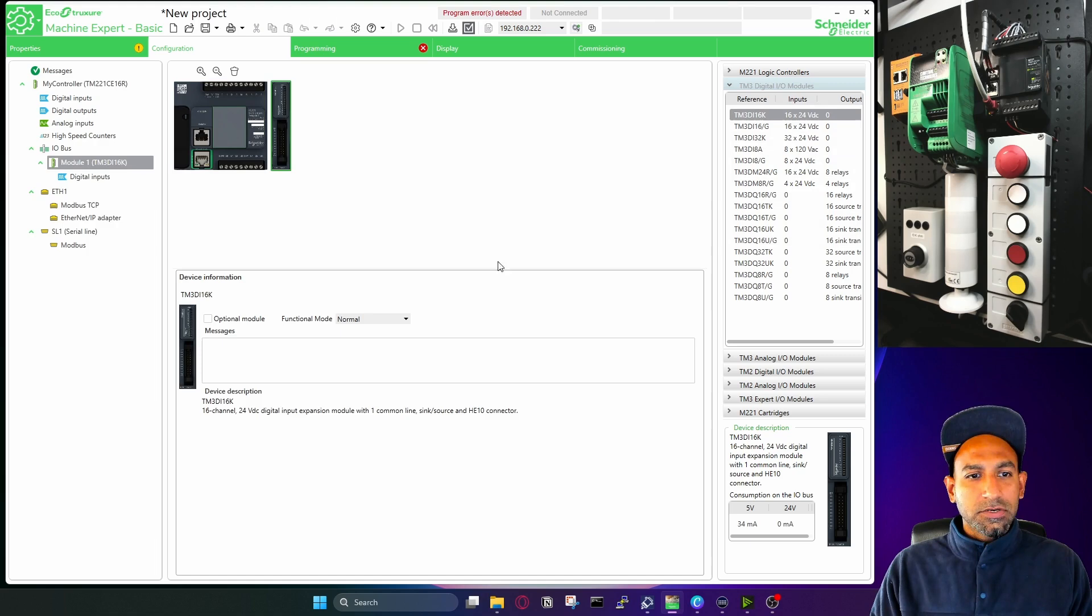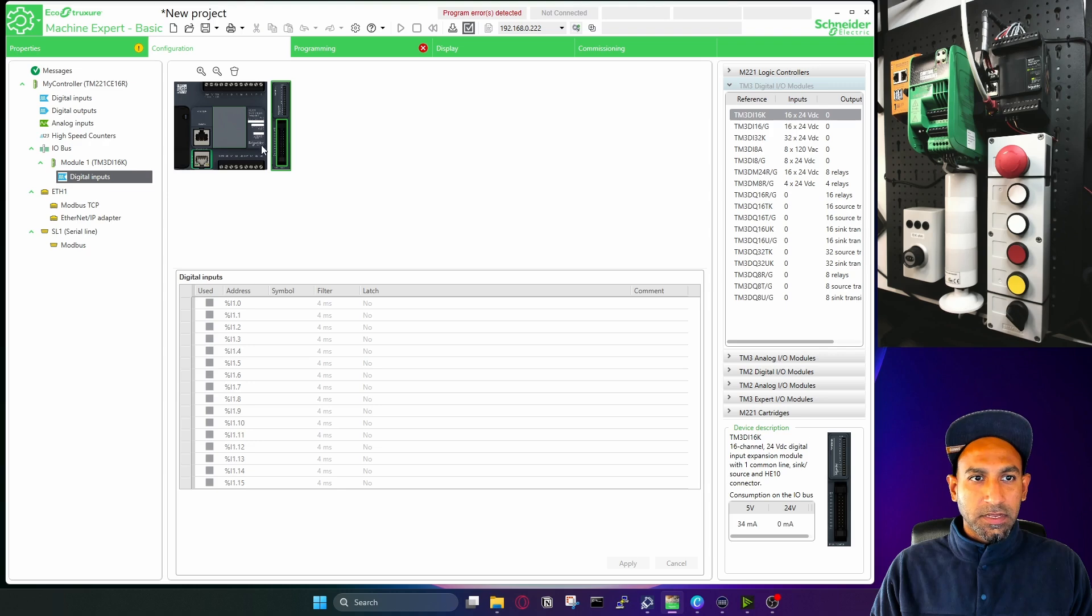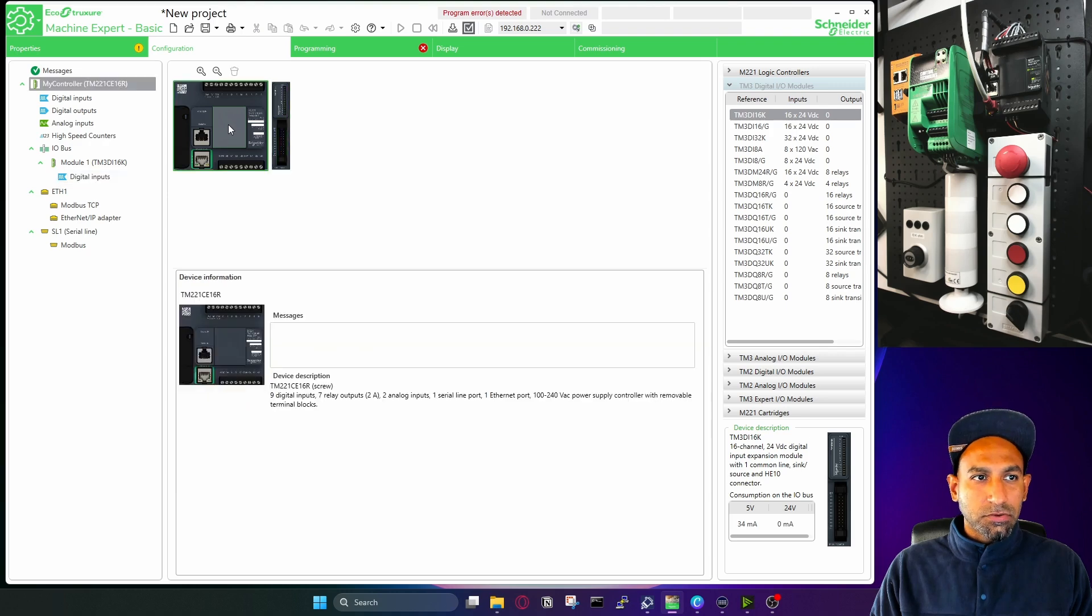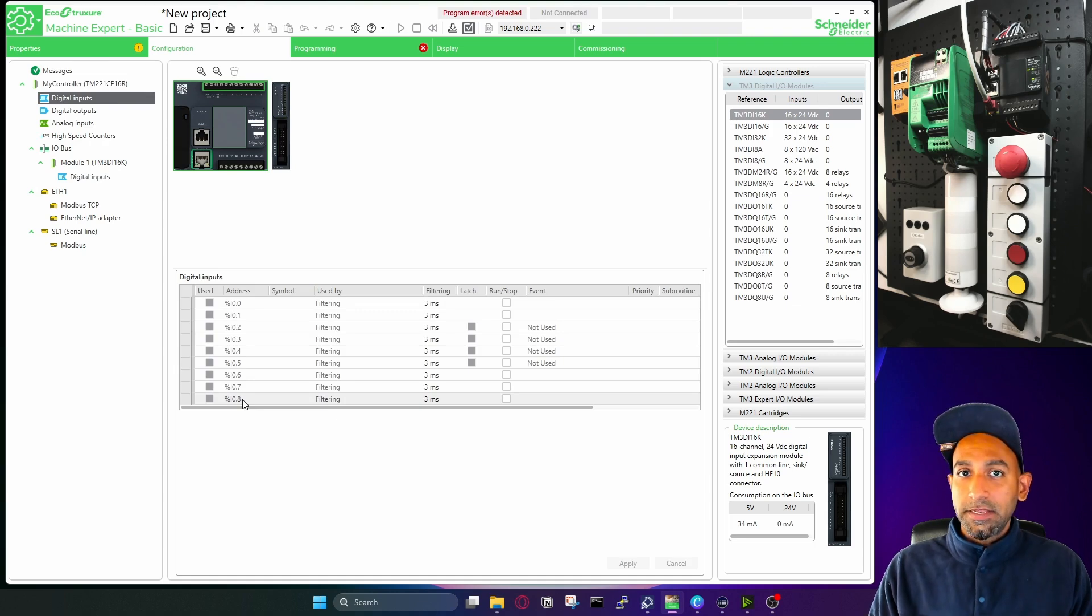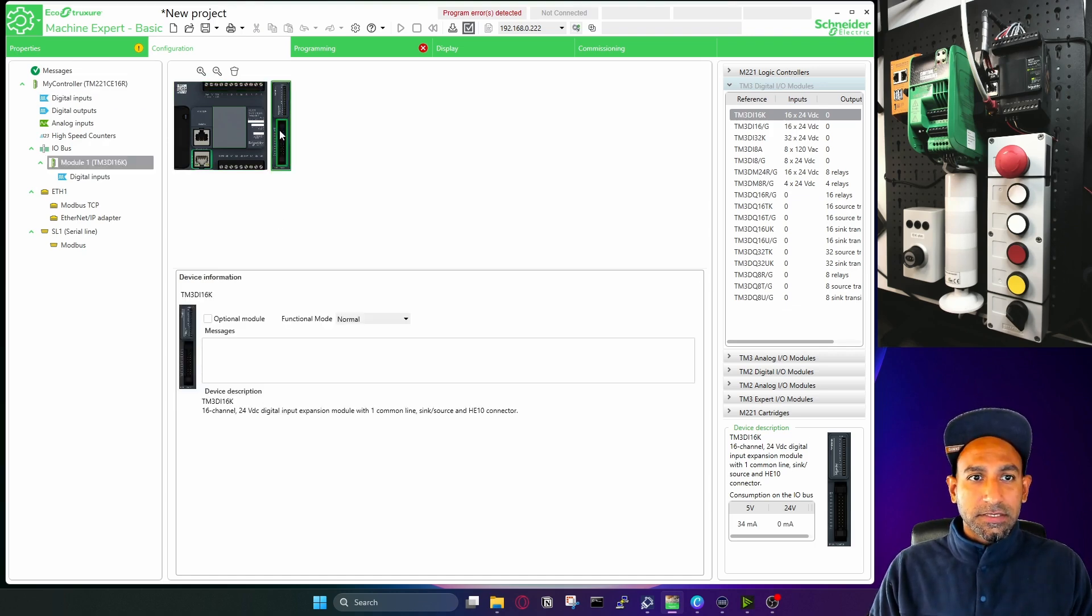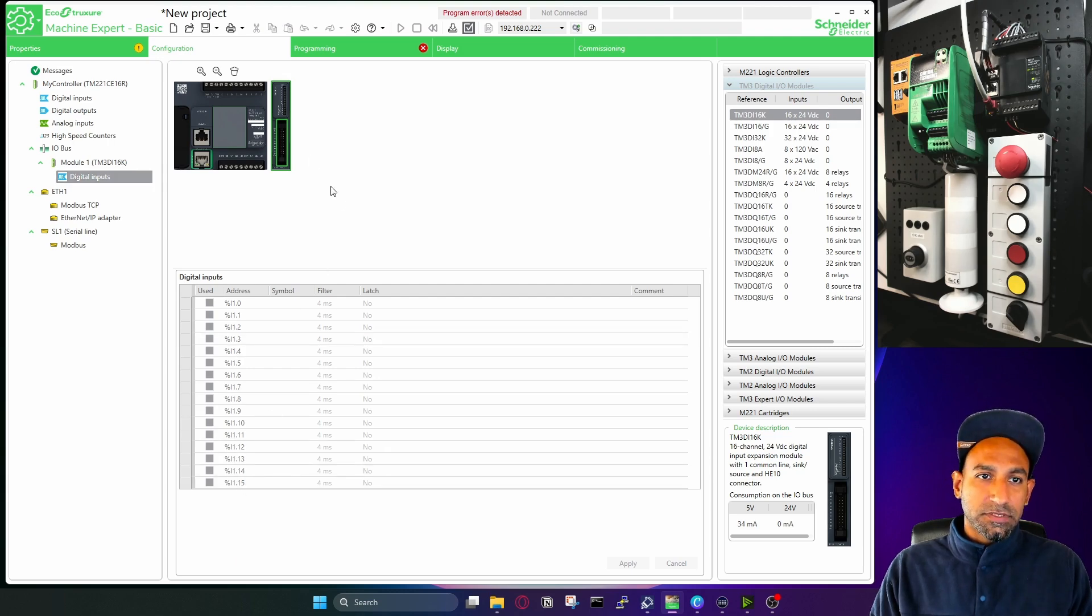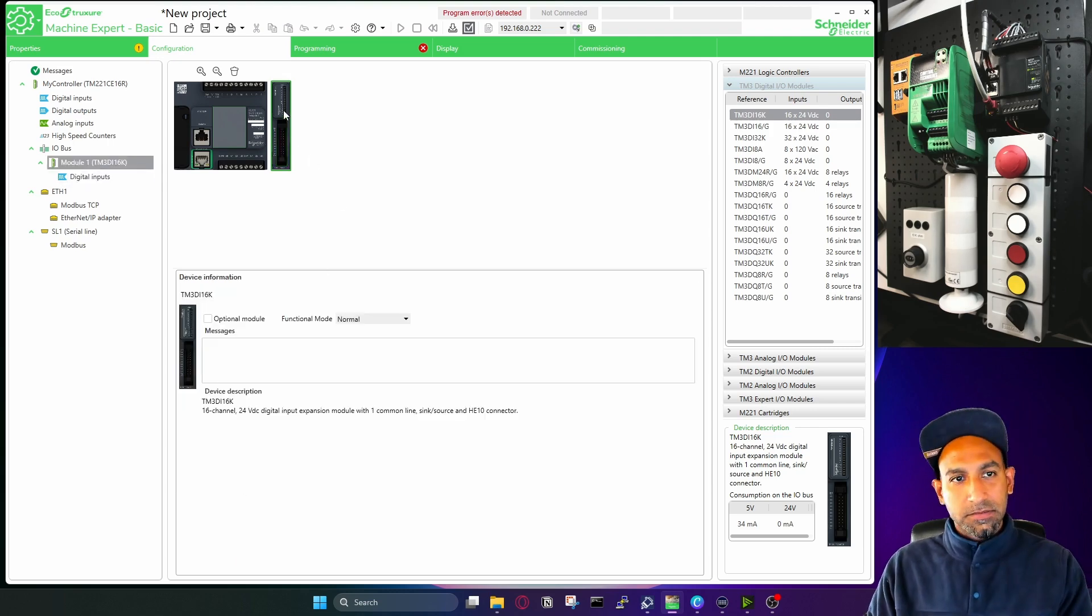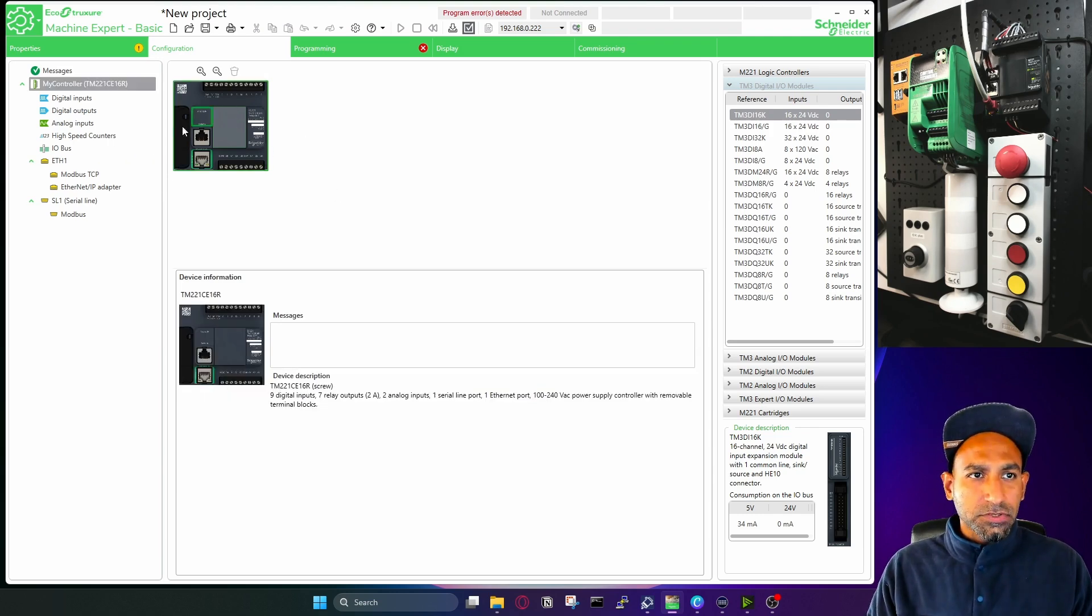And this is my IO module. So it's very easy drag and drop. And once you drag and drop, you will go to the inputs and you have the addressing of your inputs. If I select my controller, I have digital inputs starting from I0.0 to I0.8, I told you nine inputs. If you select your card, it starts from I1.0 to I1.15, 16 more inputs. Because I don't have it in my physical PLC, I don't need it, I will remove that. So that's the configuration.